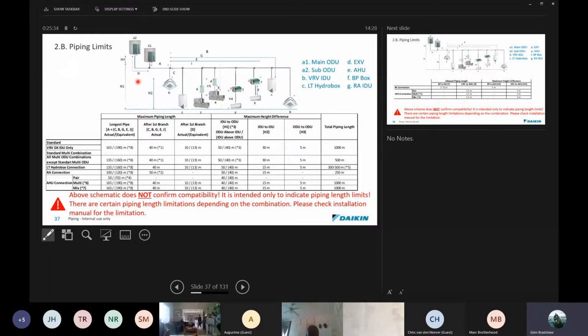The more elbows you have in a system, the faster you're going to reach the equivalent length. Okay, and we need to try and remember that we need to reduce the number of fittings as much as possible. So the longest pipe run that we are allowed for VRV condensers, these are the VRV4 condensers, the vertical discharge type, is 165 meters actual. So that would be the measurements of A through C, and B, and then right to the end over here, 165 or 100, and what's in brackets is the equivalent length, or 190 meters in equivalent length.